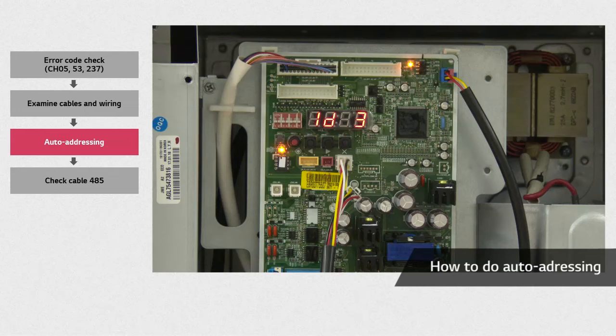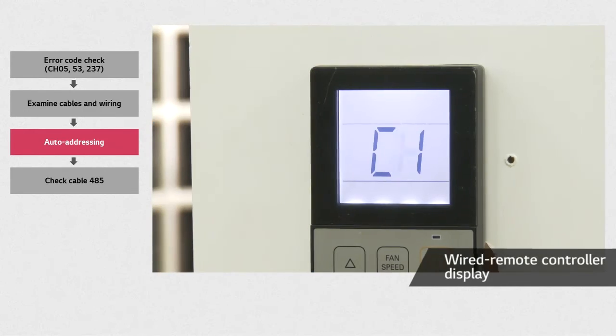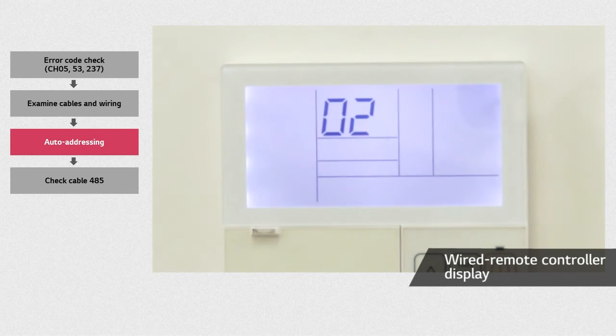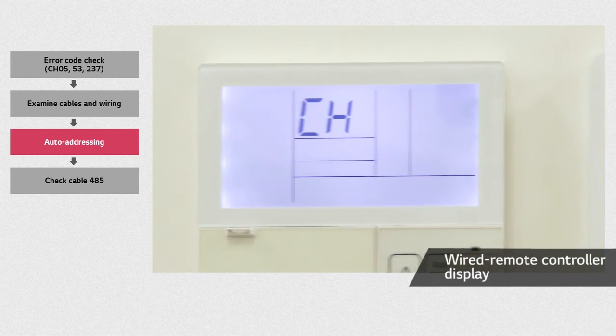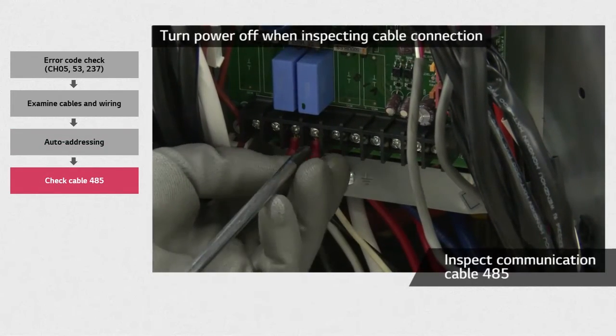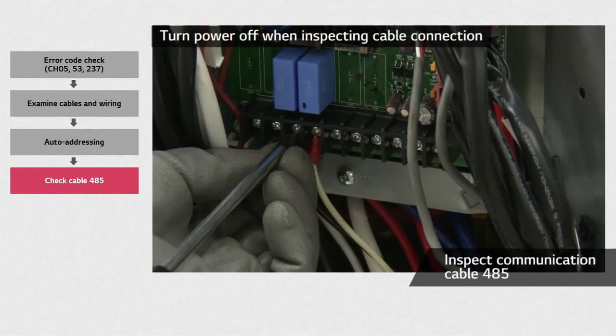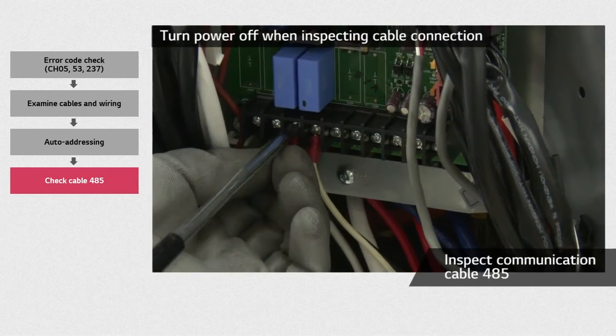Compare this number with the number of installed indoor units. Once the auto-addressing setting has been completed, you can check that the indoor unit addresses 01, 02, and 03 are displayed on each remote control. Check if the 485 communication cable terminal screw is properly tightened to the indoor unit.